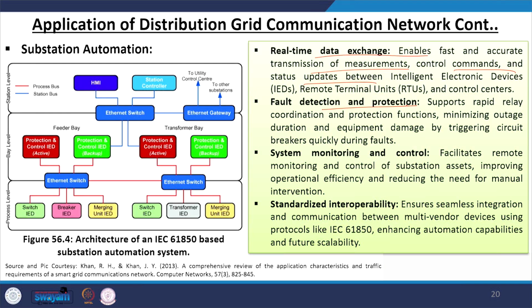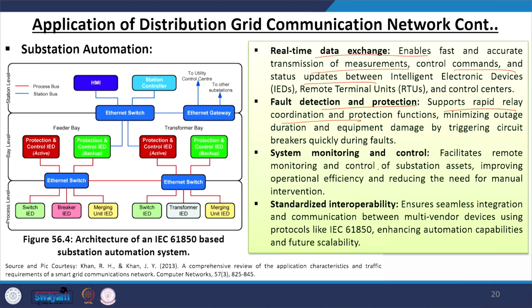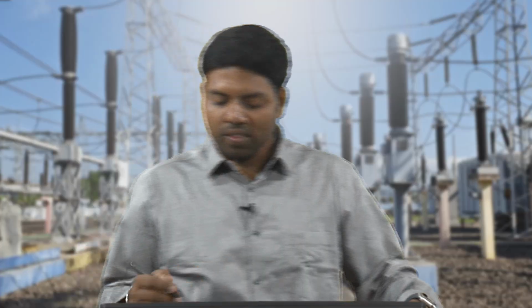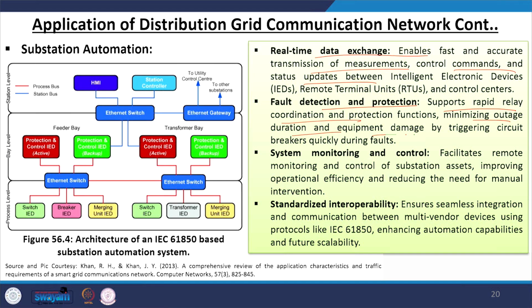Fault detection and protection, so it supports rapid relay coordination and protection functions. So, that means whenever you take data, your primary relay has to act in a very instant manner, and after some delay, if it is not operating, then the backup relay, primary backup, secondary backup, everything has to be ready. So, that detection and the protection thing, like how fast you are detecting a fault, that we have seen in the case of our fault one, that how we can use the algorithms. So, how fast that is responding, and that system is recognizing and then sending commands to the concerned relays to operate. Okay? Minimizing the outage duration and equipment damage by triggering circuit breakers quickly during faults.